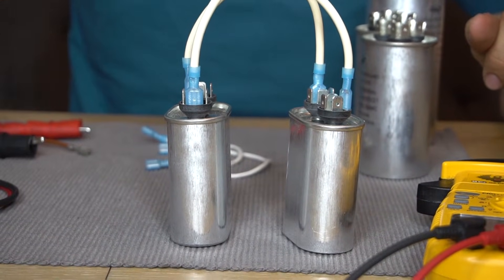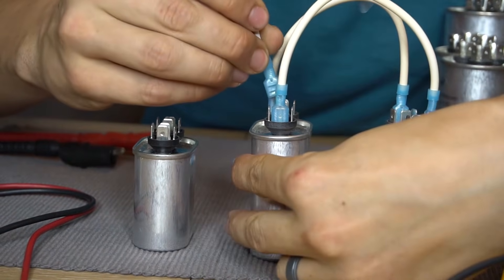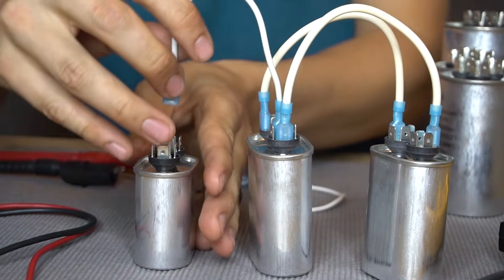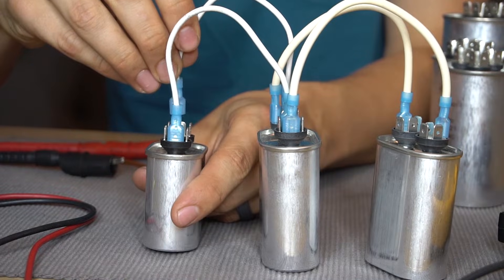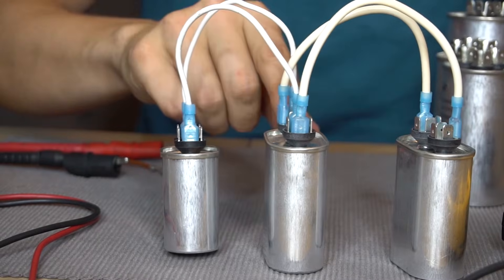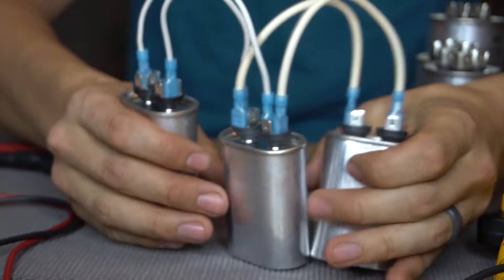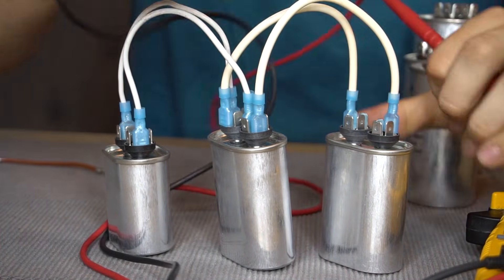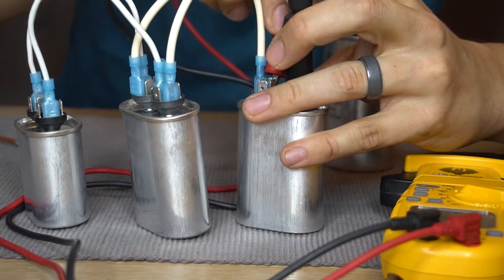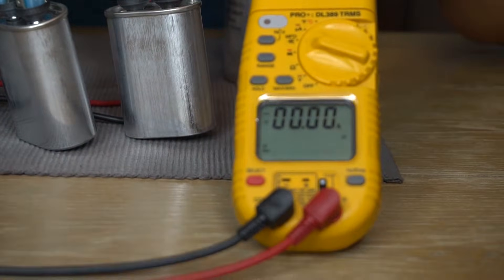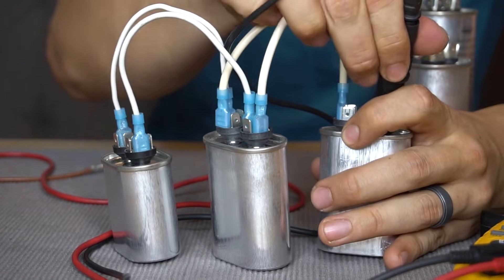Let's say you needed a 25. You can actually add another one by hooking up another capacitor. This is a five microfarad capacitor and you would basically put jumpers from one of the capacitors to the next to continue the series here. Although this is not series, this is parallel wiring. So now I have three capacitors hooked up, a 10, a 10, and a 5. And if we check it with my meter, we should get about 25 microfarads. And there you go, 25.31. So we successfully created 25 microfarads.